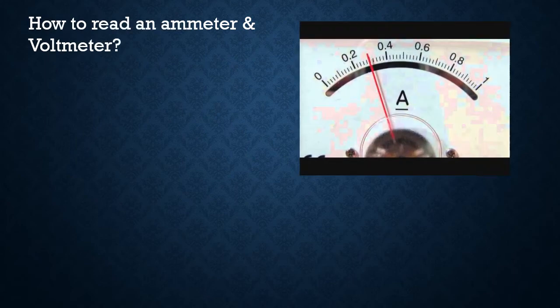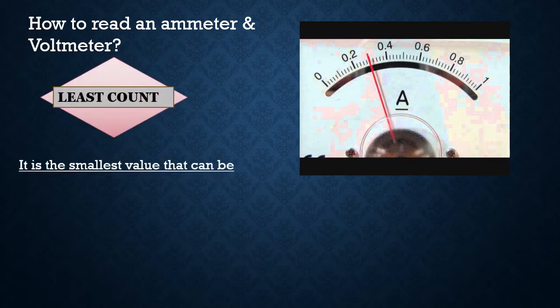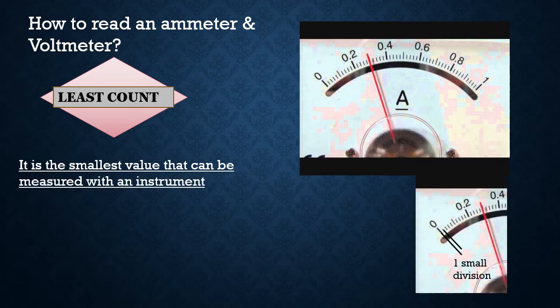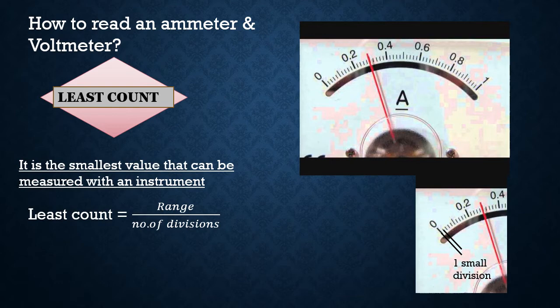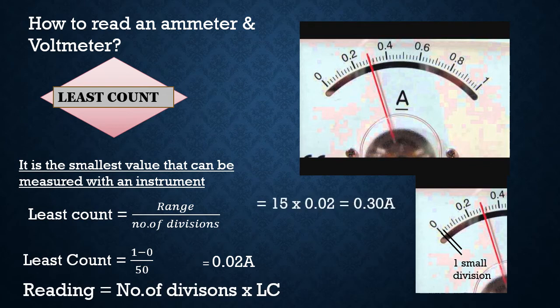To read an ammeter or voltmeter, we first find its least count — the smallest value that can be measured with the instrument. Least count equals range divided by number of divisions. For the ammeter shown, the range is 0 to 1 ampere and there are 50 divisions, so least count equals 1 minus 0 divided by 50, which is 0.02 ampere. The reading equals number of divisions multiplied by least count. With the pointer on the 15th division: 15 times 0.02 equals 0.30 ampere.